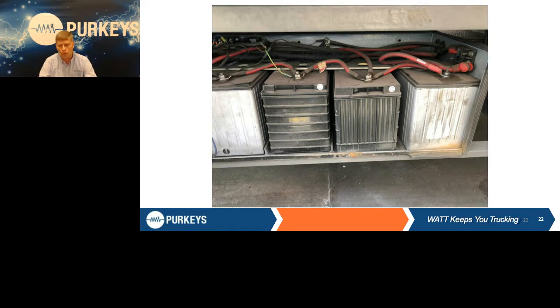So we do recommend recharge programs. There's nothing wrong with a recharged battery if it goes through the right procedures, but those batteries should all come out together, all be tested, recharged, and if you have a good match set, put those recharged batteries back in. If you don't have a good match set, you're forced to use new batteries, but make sure you give it a fair test and a fair life by going through all the right steps. With this one, obviously those should be replaced with good recharged or new ones.